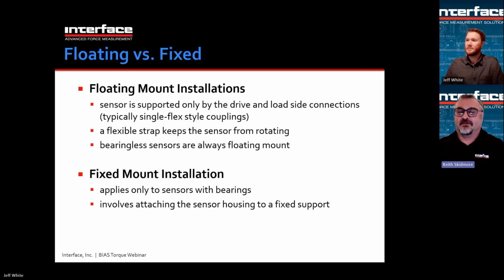Floating mount versus fixed mount. Floating mount, the sensor is supported only by the drive and load side connections, and they would use single flex type couplings for that. A flexible strap keeps the sensor housing from rotating. And when I say flexible strap, it could be a spring or a rubber strap, not a rigid mount. And then bearingless sensors are always floating mount because the bearings cannot support the weight of the shaft or the sensor, because there are no bearings.